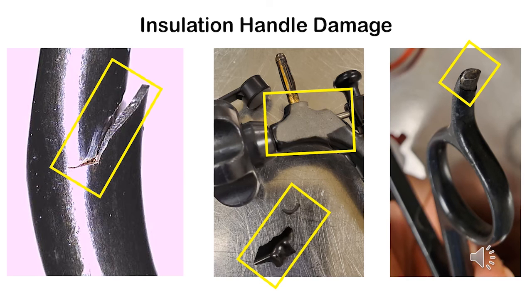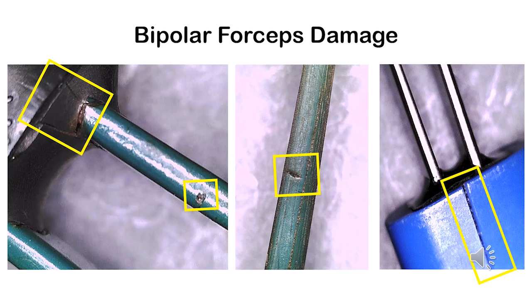In regards to insulated bipolar forceps, the picture on the left there, you can see there's two significant cracks, and you can see where it's raised up, and that's actually the weakest part of the bipolar forceps, the base, because typically you'll have two metal tines, which are each end of that forceps, into a plastic base. You can also see in the same picture there's a pinhole right in the insulation in one of the tines.